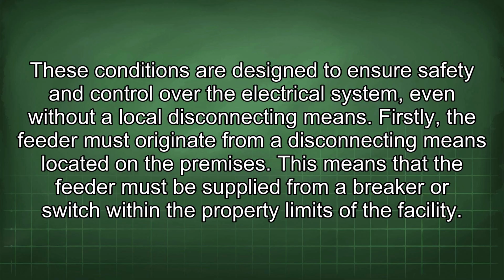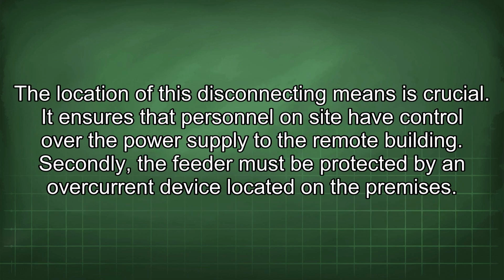Firstly, the feeder must originate from a disconnecting means located on the premises. This means that the feeder must be supplied from a breaker or switch within the property limits of the facility. The location of this disconnecting means is crucial. It ensures that personnel on site have control over the power supply to the remote building.